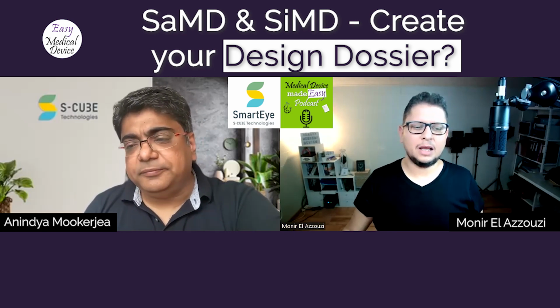Yeah, so I think it's important that we have an understanding of this SaMD and SiMD, because it's two different types of devices, two different types of files also. As you said, the SiMD has two types of files: the file for hardware, the file for software. So you have to manage twice as many things, if I can say, related to that.